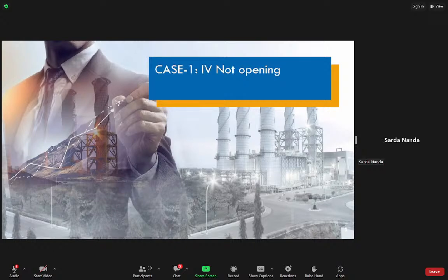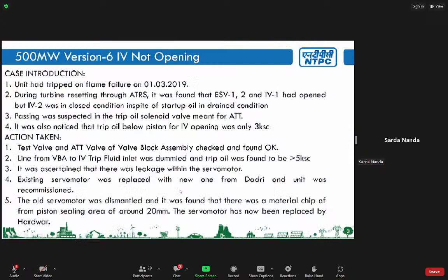There have been several problems that we have faced in the governing system. I have been associated with our version 1 machines of 200 megawatt and 500 megawatt with 4 valves, and also with 500 megawatt machines with 2 valves, the newer versions. This particular case study, where the IP stop valve, the interceptor valve, was not opening, belongs to the 500 megawatt new fleet of machines installed in Unchahar. The unit had tripped, and while reviving the machine during ATRS, it was found that 3 of the 4 stop valves had opened, but IP stop valve 2 did not open at all.